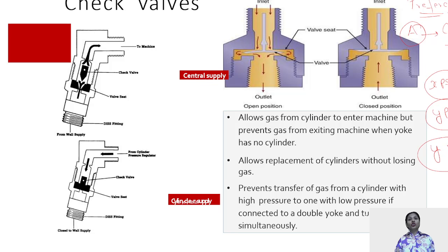And by any chance, the pipeline gets stopped or some problem happens at the central supply, you have no reserve left of the oxygen at the back of your machine. So the pipeline pressure is always preferred and is always slightly higher than your cylinders which are attached to the anesthesia machine. And ideally, your cylinders should always be in an off position when you are getting a pipeline supply of the oxygen.